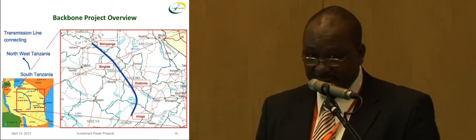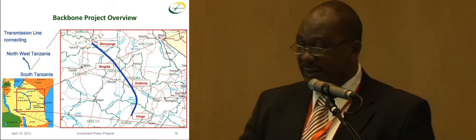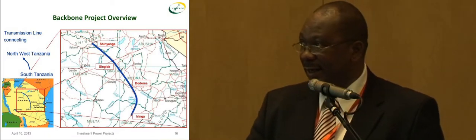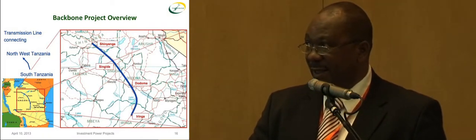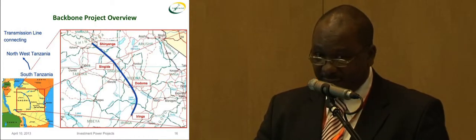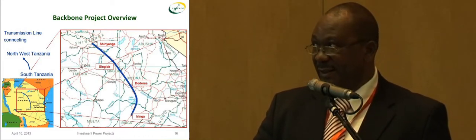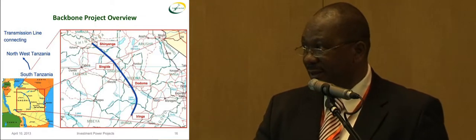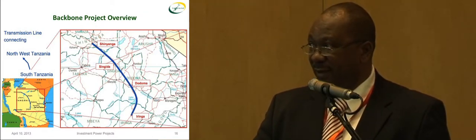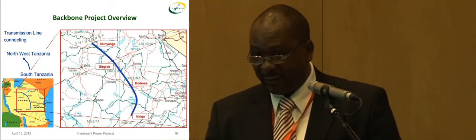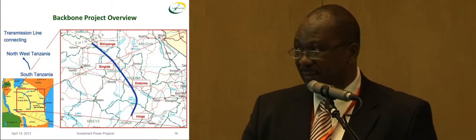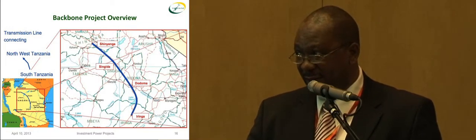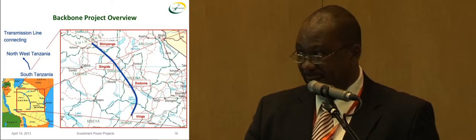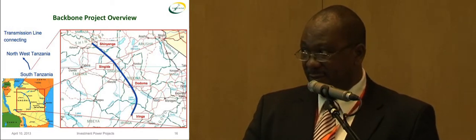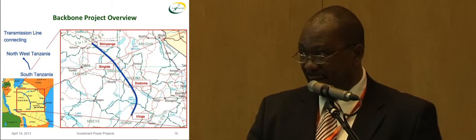What are the opportunities that the backbone project presents to Tanzania? There are a number of them. Obviously, it provides delivery of power from the south, where all the generation is located, to the north. It will bring improved power quality in terms of voltage improvement, as the current line is already overloaded. It will improve reliability of supply, as in the design we've taken care of the N-1 criteria. Losses will be reduced, particularly by removing the overload on the line.